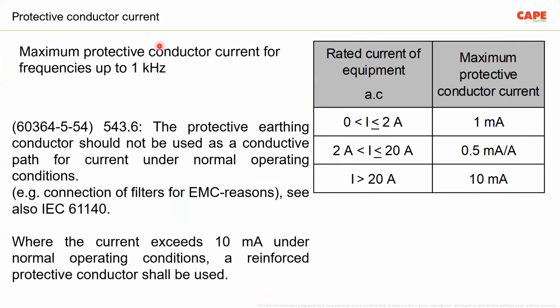But let us look at what the rule is. What is the minimum requirement? Maximum protective conductor current. What is a protective conductor? The protective conductor is the earth wire. The earth wire is not a current carrying conductor. It's a dead wire. For loads up to 20 amps, the maximum allowed leakage current, or maximum allowed continuous current, in the PE conductor is 10 milliampere. So there is a limit for the continuous current flow through the earth conductor.